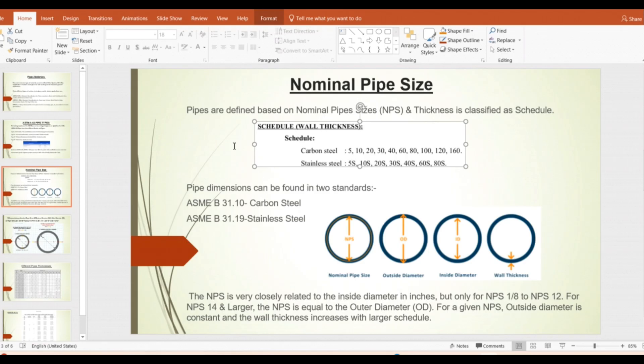For carbon steel, the thickness schedules are: Schedule 5, 10, 20, 30, 40, 60, 80, 100, and so on. For stainless steel, the same schedule numbers apply but with an 'S' added — for example, Schedule 5S, 10S, 40S. The pipe dimensions can be found in ASME B31.10 for carbon steel and ASME B31.19 for stainless steel.